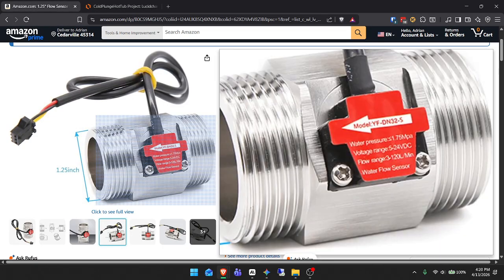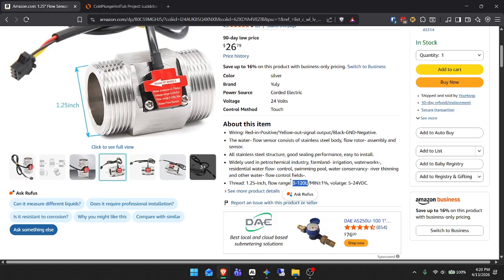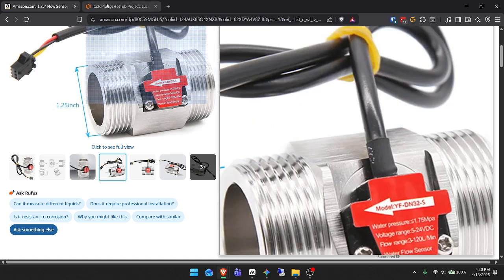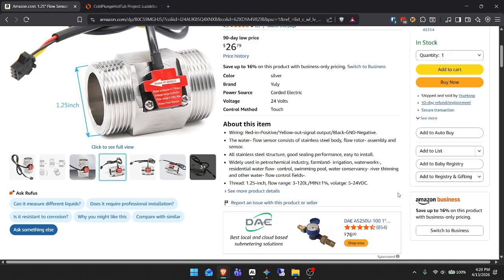When you look at your flow sensor, it's measured in liters per minute. The range on mine is 3 to 120 liters per minute. What you want in a system - remember mine is 80 liters per minute - is your maximum flow to be around double the operating flow of your plumbing system. In my case it's 80, and this sensor goes up to 120. It's not quite double, but it's good enough - I'm okay with that.